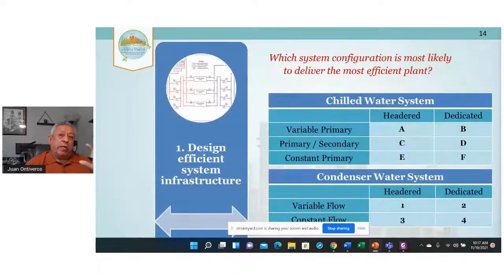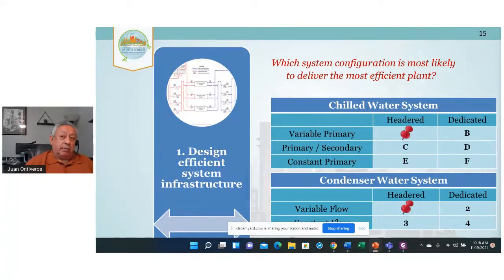The other part of designing cooling plants is that you have a lot of options in how you connect the chillers to your system, and how you connect your cooling towers to your system. You can decide to header each chiller into one big header, or have dedicated pipes that go out to the system. You can do a variable primary, a primary-secondary, or a constant primary. In the condenser water, you can do variable flow or constant flow. Those are the options. I say the most efficient mode is to do a variable primary and variable flow on the condenser water. That's the way you're going to do this.